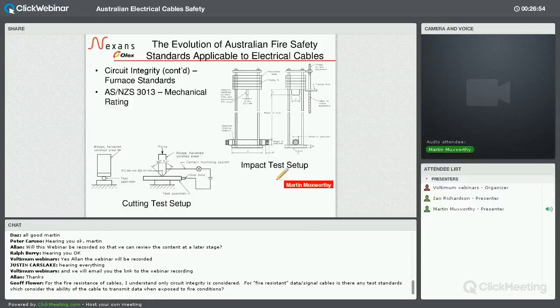Just to keep going on the final part of 3013, there's a mechanical impact and cutting test, and these little images give you an idea of how the impact and cut test work. Impact is a set of weights. It's got a bar positioned in the center of them, and the weights are simply dropped on the cable a number of times. And of course, the cable's got to continue to carry current, and it's not allowed to short circuit to either the platform or the cutting object, or the impact object, I should say.